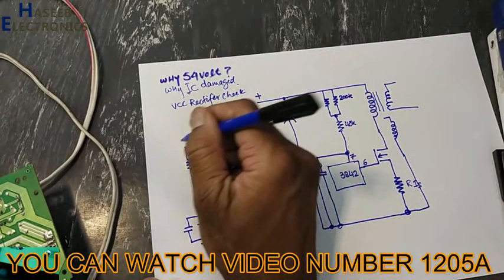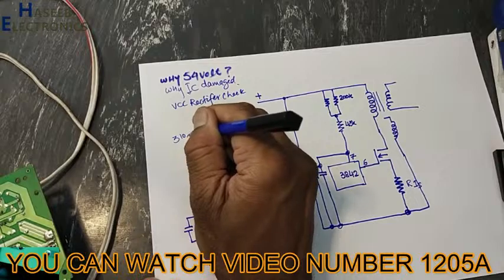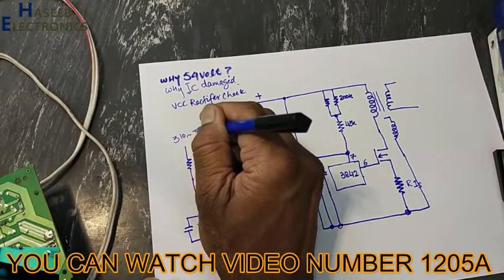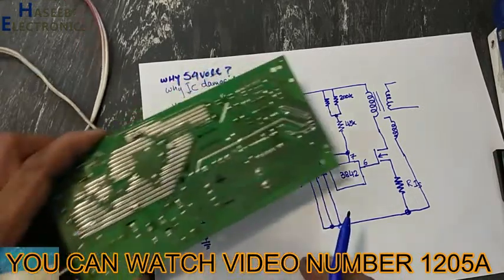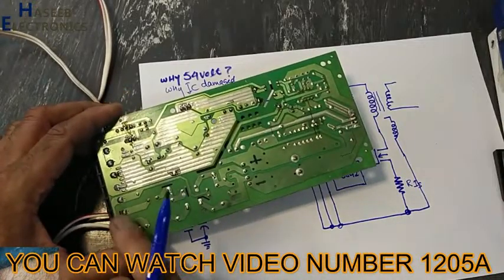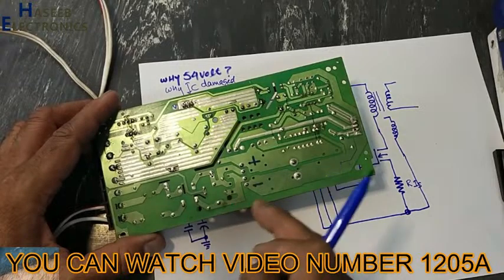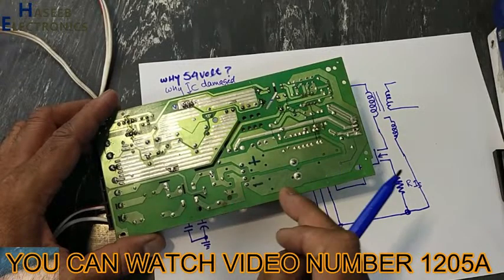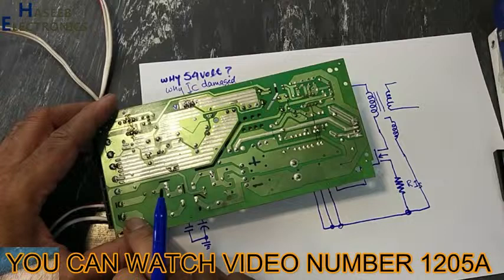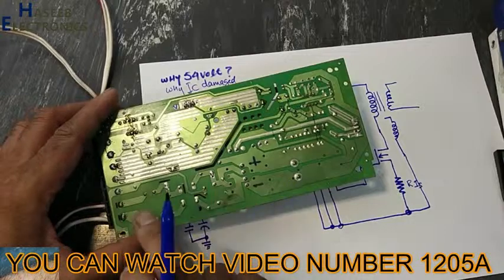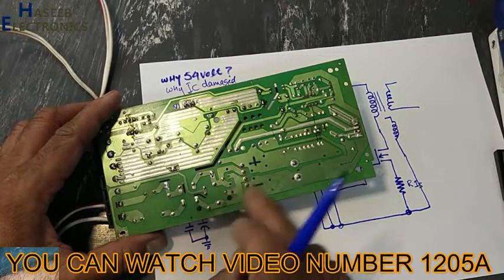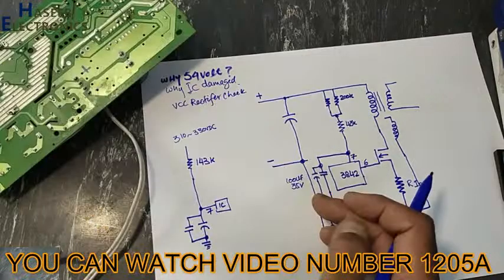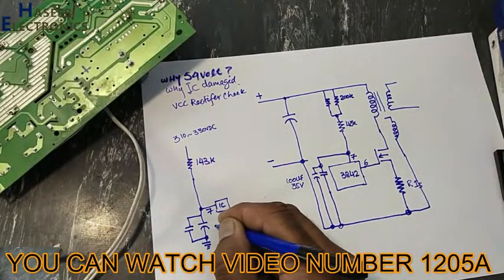Here we applied 310, 330 volt DC, because the voltage applied at the line terminal is rectified and peak voltage is stored here. 220 here or 230 here becomes 330 here. AC voltage multiplied by 1.414, when we connect it to this higher voltage, and this capacitor is...